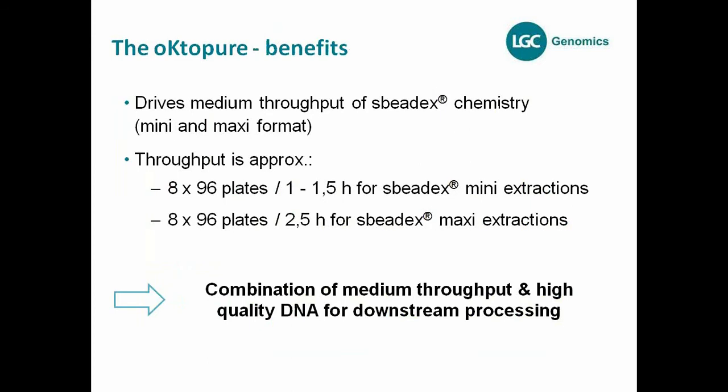A few numbers on throughput: it is a medium throughput machine. You can process eight times 96 samples in one to one and a half hours for the sbeadex mini extractions, and eight 96-well plates in two and a half hours for the sbeadex maxi extractions. The only reason the maxi takes a little longer is the volume — the robotic head is equipped with 200 microliter tips and must go several times to fill the right volumes for the larger reaction.